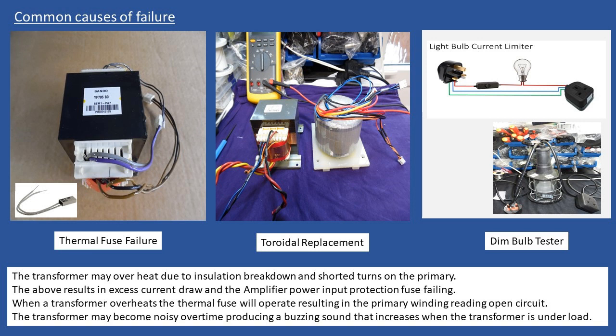In the video where I'm showing next to the EI type transformer is a great example where the original transformer cannot be sourced. This is actually a Pioneer A10 type transformer, and the cost of this is just as much as the amp. But the Pioneer A10, A20, A30 are good amplifiers, so you don't want to throw it away. So what I've had made here is a toroidal replacement, and you look at it and you say, hey, I can see what it's doing. It has the same VA rating. It has a thermal fuse built into that toroidal, so that's good from a fire protection point of view. And then what I've manufactured here are base plates.